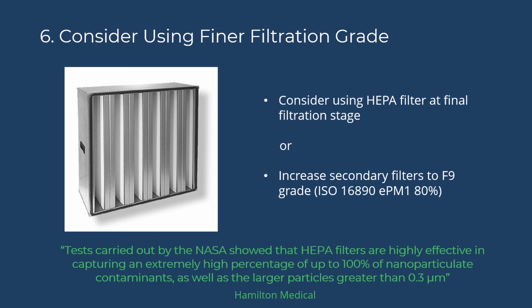If any of your production areas have moved to a higher risk category as a result of the pandemic, they may require HEPA filtration. It is worth mentioning that not all air handling unit fans are capable of creating the extra airflow needed to push air through HEPA filters, although secondary filters can be increased to an ePM1 80% filter according to ISO 16890, which is the old F9 grade.